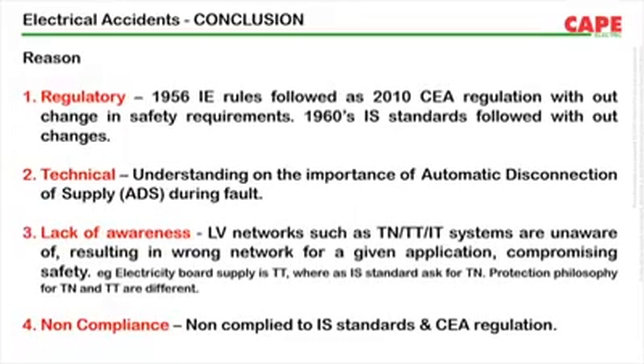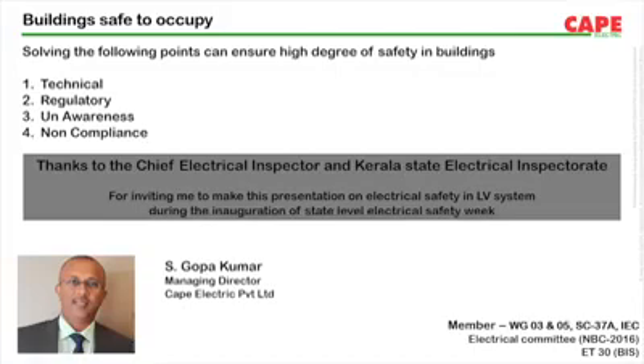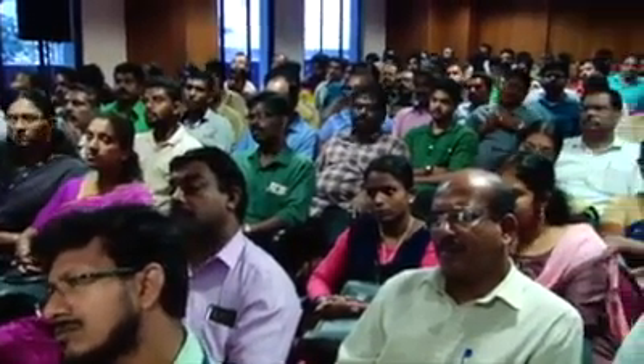I repeat as a conclusion again. The problems are understanding of regulation and standards, lack of awareness of the technical requirements of automatic disconnection of supply and the continuity of supply during first fault, and non-compliance of the wiring. And if these points are well taken care of, we can build electrically safe buildings where accidents and fire due to short circuit are negligible.